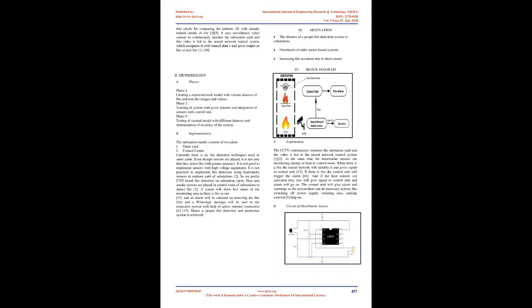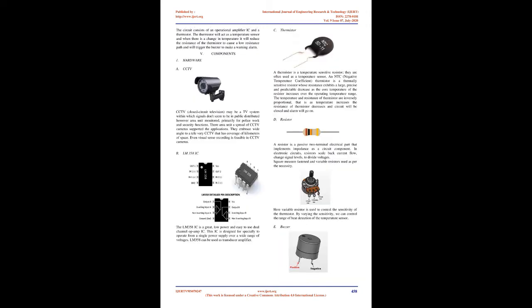So we prefer CNN-based fire detection for substation yards. Heat and smoke sensors are placed in the control room of substations to detect fire. A screen will show the live status of the monitoring area, whether there is fire or not. An alarm will be initiated on detecting fire, and a WhatsApp message will be sent to the respective person with the help of an active internet connection. Hence a proper fire detection and protection system is achieved.